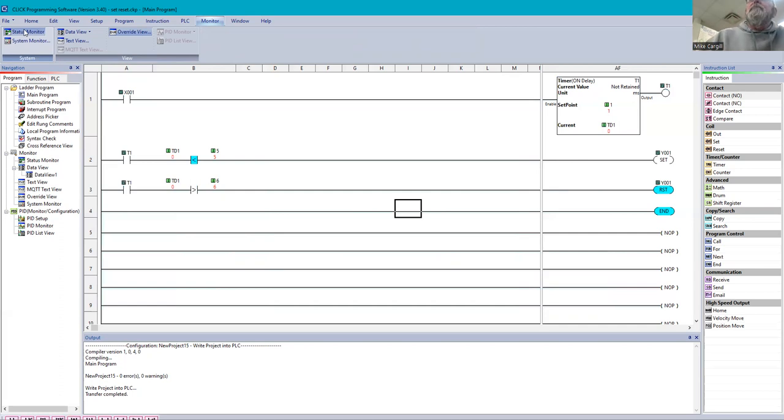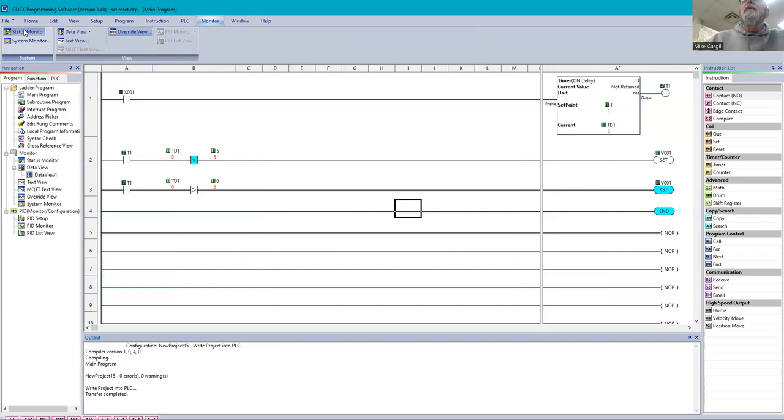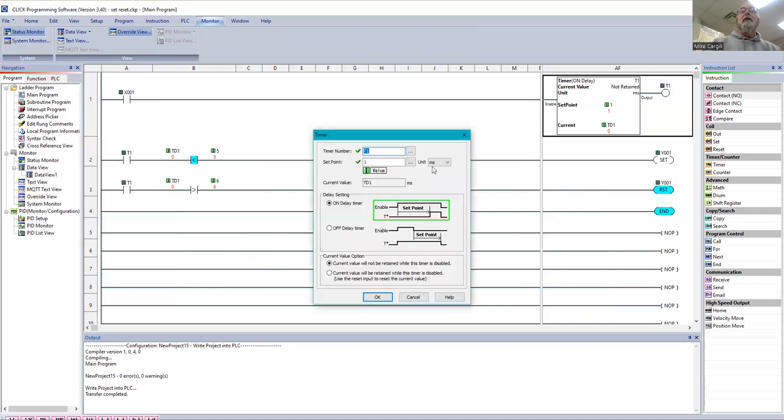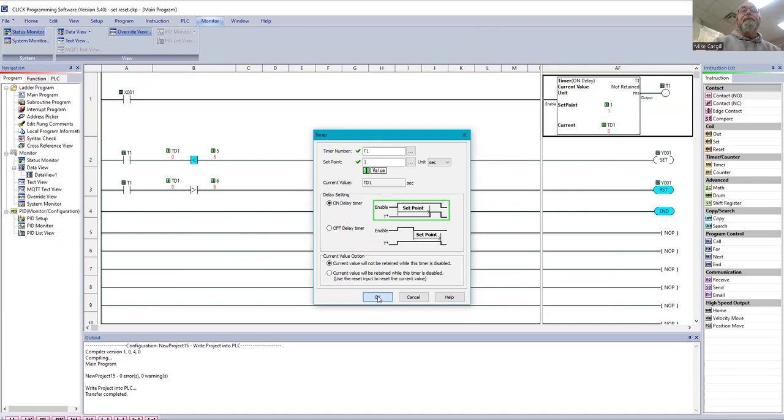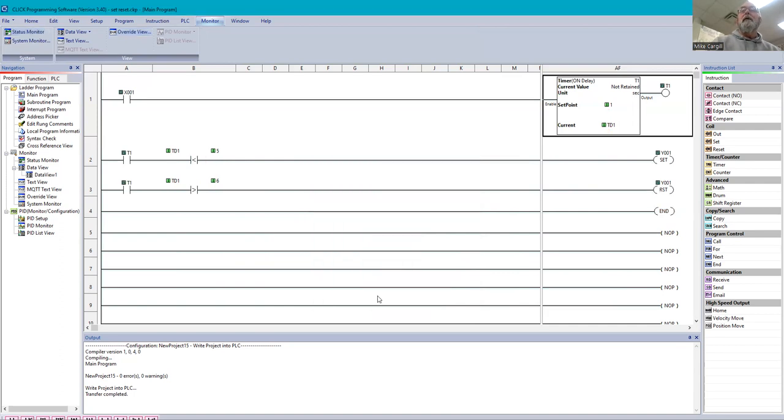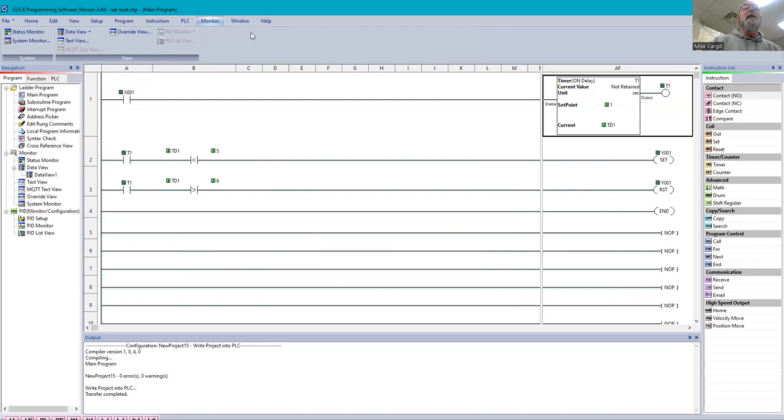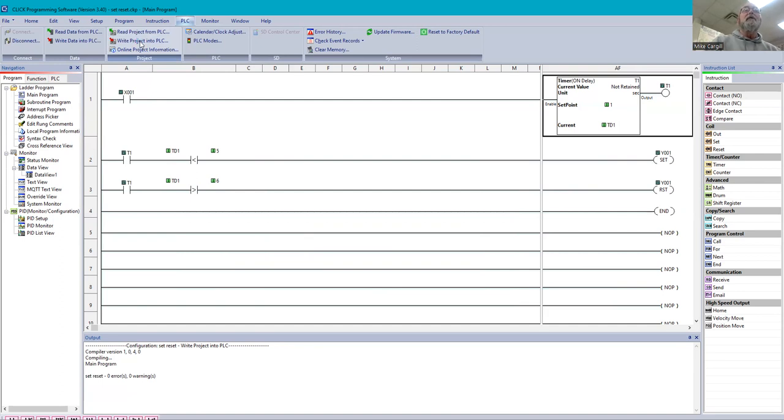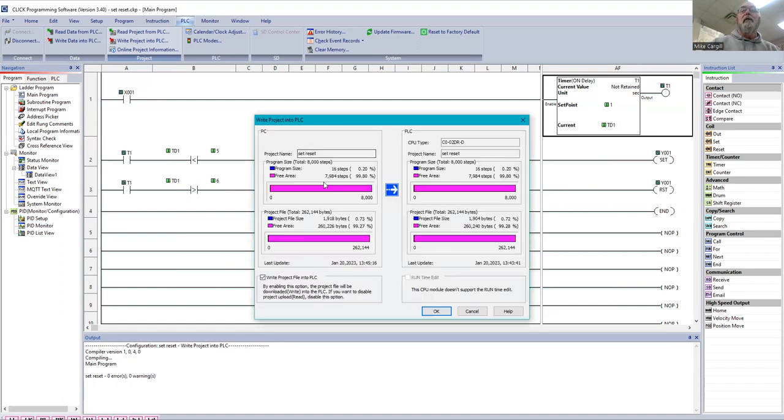So here we go. How come it did that, I wonder. Do I have that in milliseconds? Let's go take a look at this. Yeah, I do. So I had one millisecond, I should have seconds. One second. I should have looked at that. Okay, we're going to send it back down to the PLC. It's writing it. There it is.